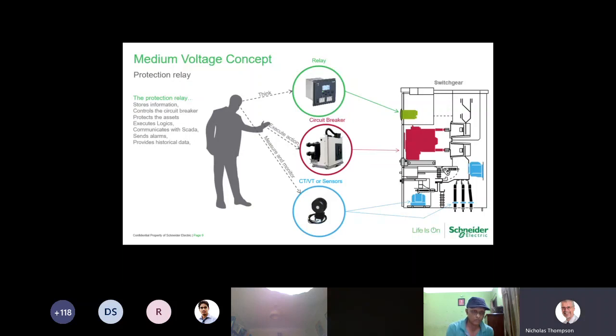So in all switchgear, whether it's going to be primary or secondary distribution switchgear, we've got this concept of where we've got the brawn, which is our circuit breaker. We've got some form of measuring, which is the current transformers or voltage transformers, or low power current transformers or low power voltage transformers. They're providing the means for the protection relay to work. And the reason we use CTs or VTs is to primarily step down the very high current flowing through the primary circuit to something more manageable.